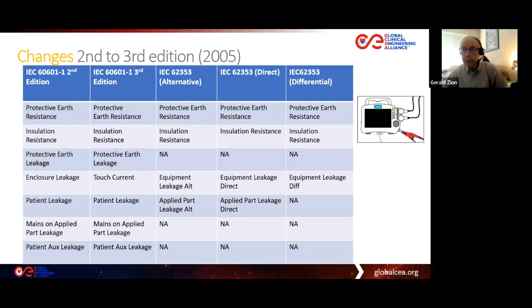All right, there are some terminology changes from the second to the third edition of the IEC 60601-1. In particular, the one I want to focus on is the one that says enclosure leakage. That has been changed in the third edition to be named touch current. And the reason it's touch current is because that's actually what our concern is here. That would be what happens if the patient somehow touches the medical device while they are connected to it, or the clinician touches the medical device while they are touching the patient. There is a risk of microshock there. We want to be sure that we have measured it and understand how much, where is it flowing, and we need to understand that it's touch current.